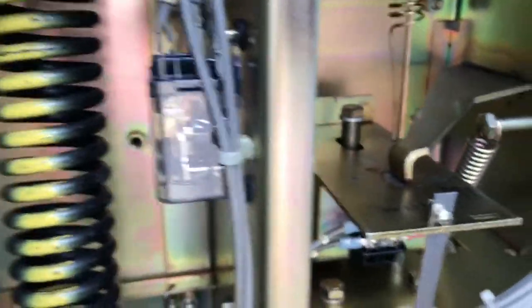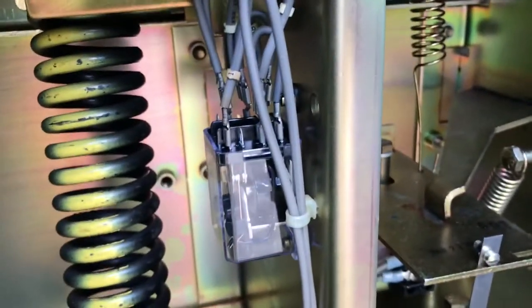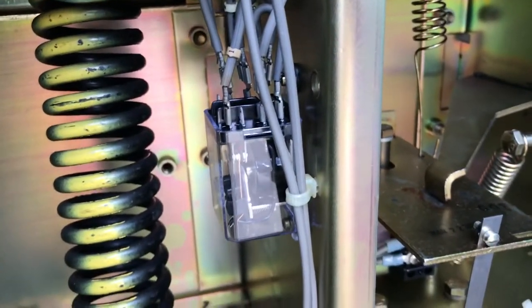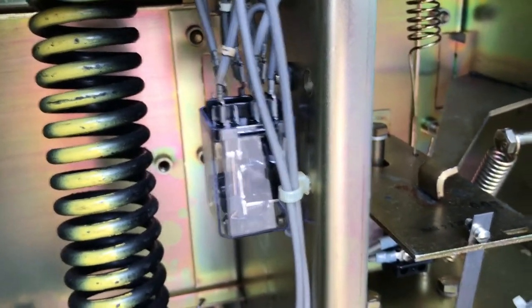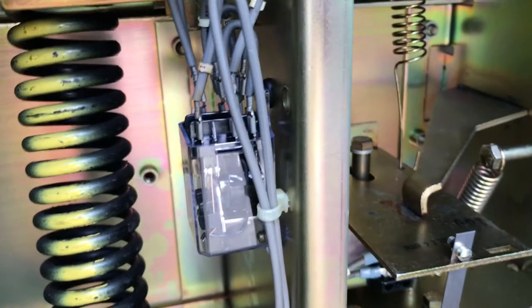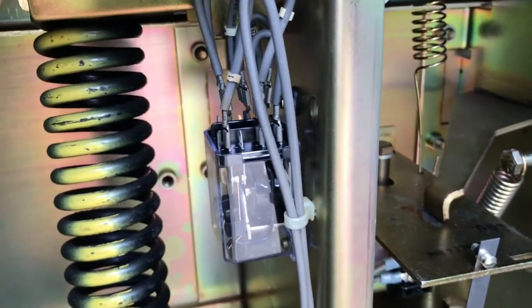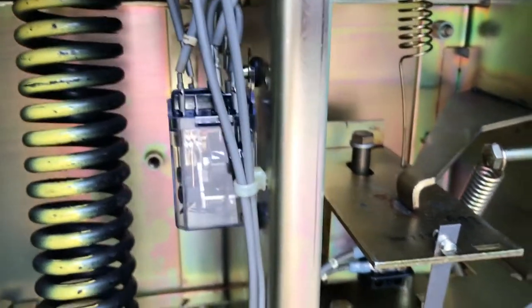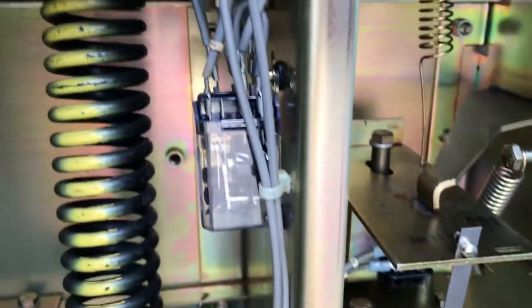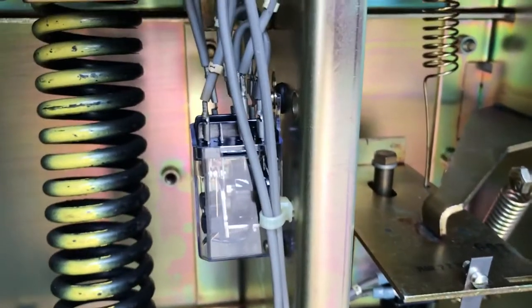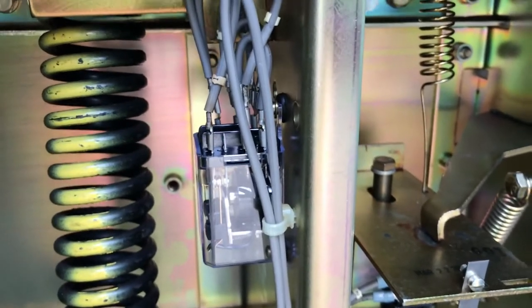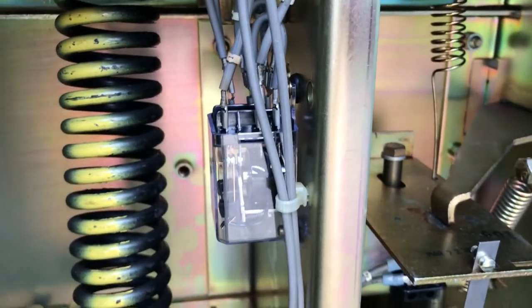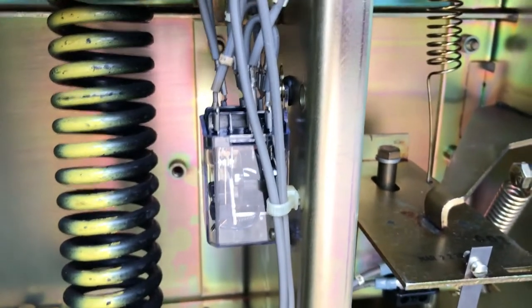I've got my hand on the control switch now. I reinstalled the springs on the undervolt, so it's going to trip free. I'm going to show that if it trips free and the control switch remains closed, that anti-pump relay is going to remain closed the entire time as well.